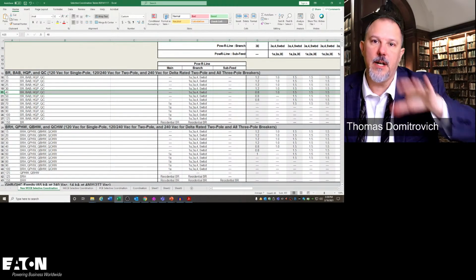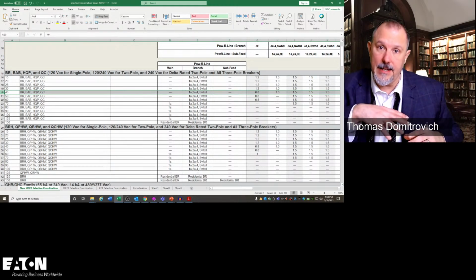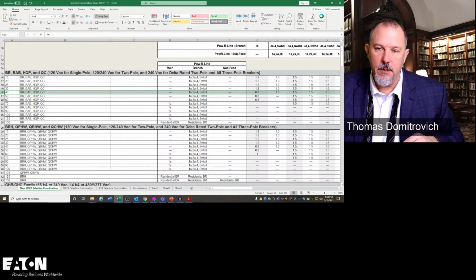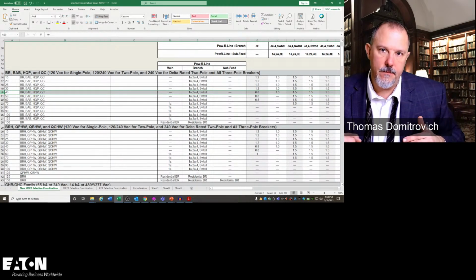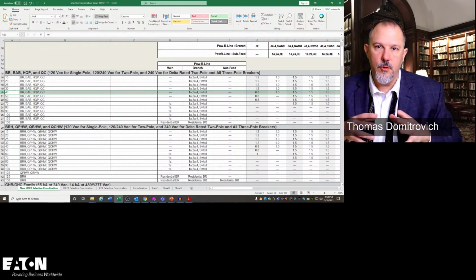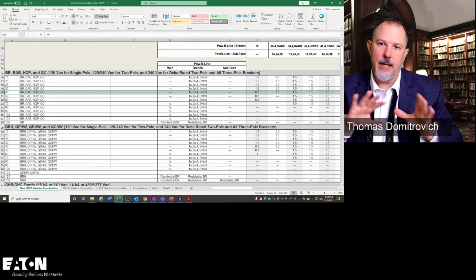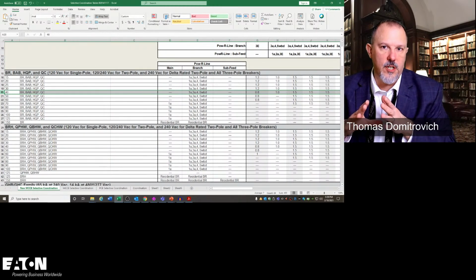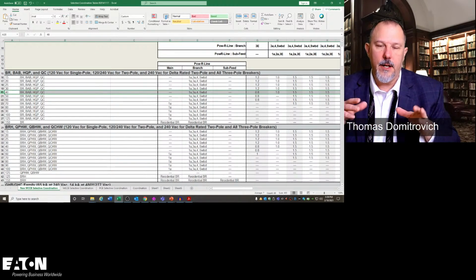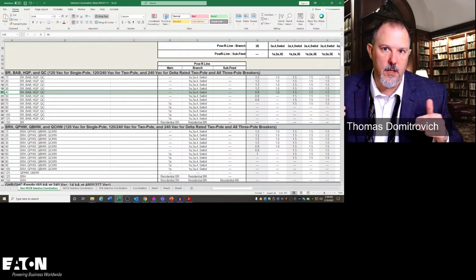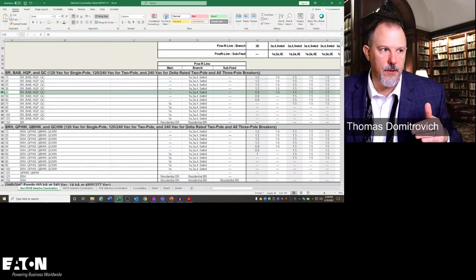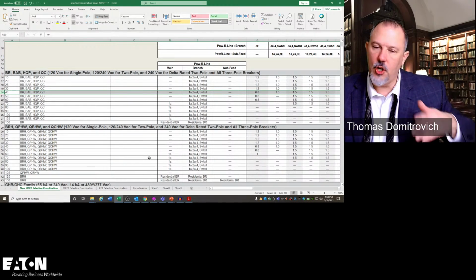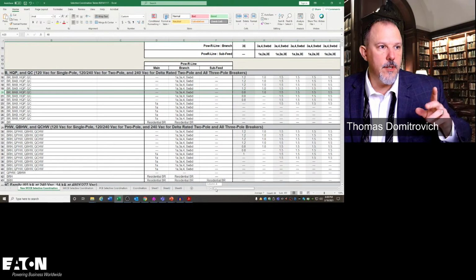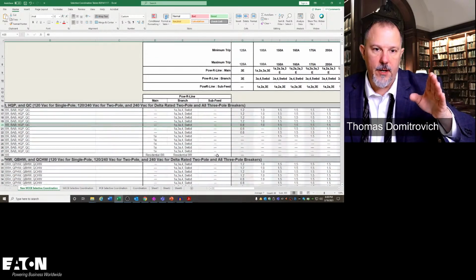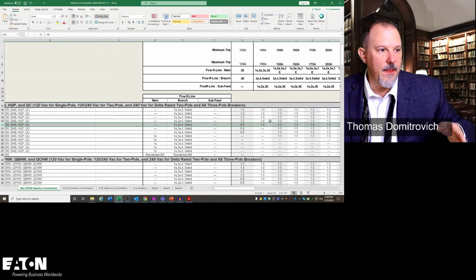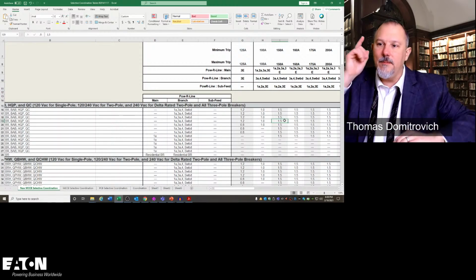Now, what this table does, we have tested everything across the top with everything down the left-hand side. Some manufacturers will use the let-through, and that's a discussion for a different day on how that works. It's more of a mathematical and an analysis method to determine selective coordination at fault current values. But we actually tested, did a huge program. So what you're going to see across the top is my upstream breaker, down the left-hand side is my downstream breaker, and these values in the middle are values of fault current. So MC had it right.